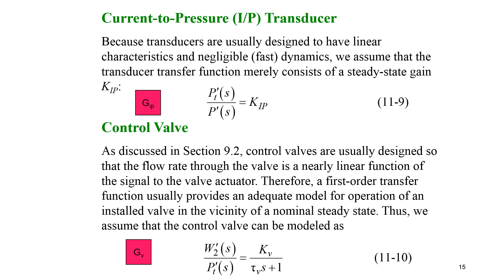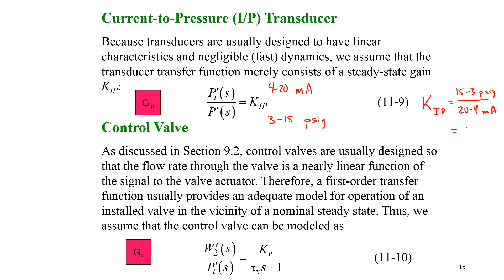We also have a current-to-pressure transmitter. The standard in the process control industry is 4–20 milliamp for current and 3–15 PSIG for pneumatically actuated valves. To get the gain for the I-to-P converter KIP, we calculate (15 − 3) PSIG divided by (20 − 4) milliamp, which gives KIP = 0.75 PSIG per milliamp.